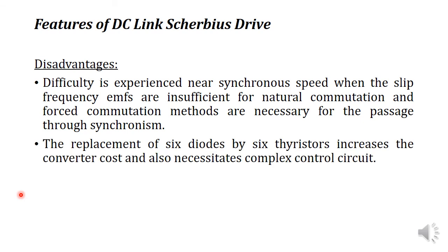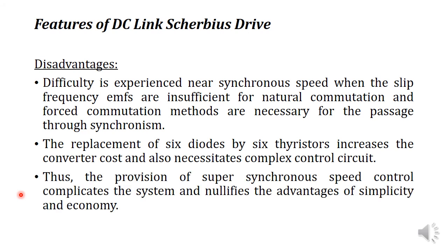The second disadvantage is that replacing the six diodes of the Kramer drive with six thyristors increases converter cost and makes it more complex to design a control circuit for the six additional thyristors. The last disadvantage is that the provision of super-synchronous speed control complicates the system and nullifies the advantages of simplicity and economy.